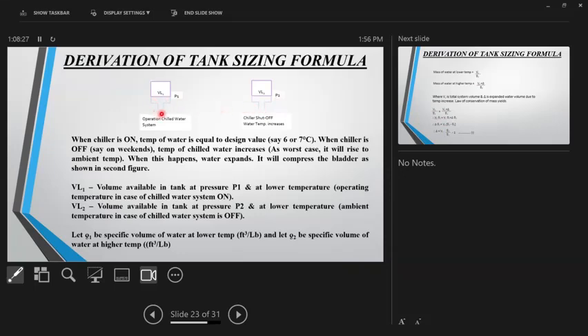When the chilled water temperature was 6 degrees centigrade, my air volume was VL1 and pressure was P1. When my temperature increased, my bladder was pushed. I got this VL2 volume, and the pressure was P2. So VL1 is the volume available in the tank at pressure P1 at lower temperature, and VL2 is the volume available in the tank at pressure P2 and at higher temperature. Again, a spelling mistake here: at higher temperature.